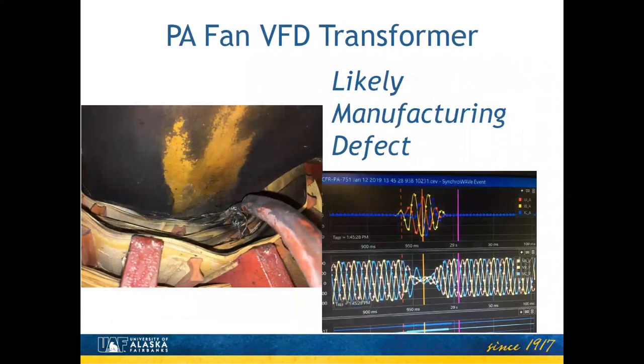Okay, the failure that we had in the VFD transformer, that was an odd one, and not something that either we or the manufacturer had encountered before. But from the investigation that was done on it, it appeared that there's a red-coated wire that goes down into that coil of the transformer, and it appears that it somehow failed. It either broke or fused or something, caused a short circuit within the transformer, and it blew itself out in that single phase. The photo on the right is showing what the protective relays recorded at that time.